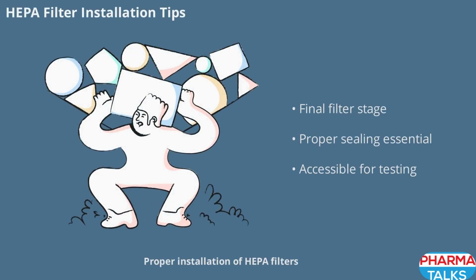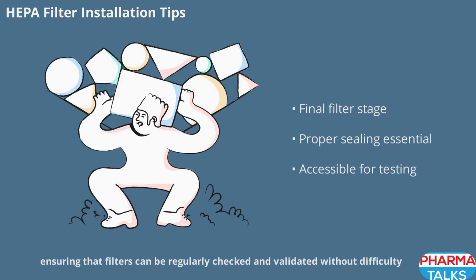Proper installation of HEPA filters is vital for effective contamination control. They should be installed as the final filtration stage, with careful attention to sealing, using either gel seals or gaskets to prevent bypass leakage.